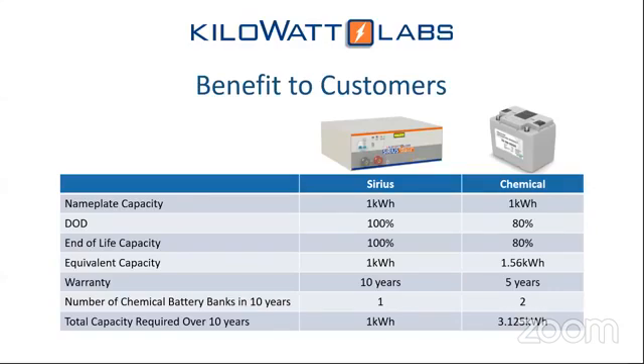I've done a small exercise comparing a chemical battery and a Sirius battery. If you look at the nameplate capacity, I've assumed 1 kilowatt hour. For Sirius, the depth of discharge is 100%, and for a chemical battery I've assumed 80%. At end of life capacity, Sirius is again 100% and the chemical battery is 80%. So at end of life, whether 5 years or 10 years, the Sirius will still give 1 kilowatt hour. To get 1 kilowatt hour at end of life, you buy 1 kilowatt hour of Sirius, but you have to buy 1.56 kilowatt hours of a chemical battery.